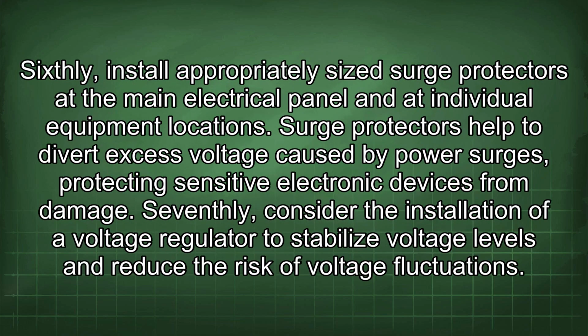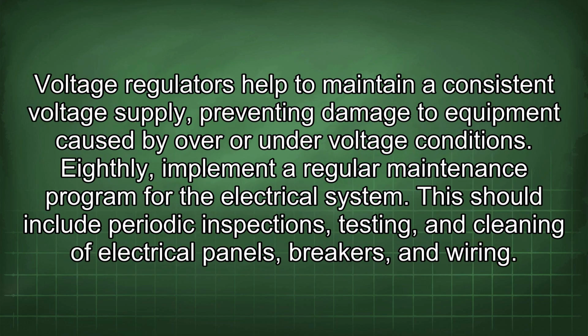Sixthly, install appropriately sized surge protectors at the main electrical panel and at individual equipment locations. Surge protectors help to divert excess voltage caused by power surges, protecting sensitive electronic devices from damage. Seventhly, consider the installation of a voltage regulator to stabilize voltage levels and reduce the risk of voltage fluctuations. Voltage regulators help to maintain a consistent voltage supply, preventing damage to equipment caused by over or under voltage conditions.